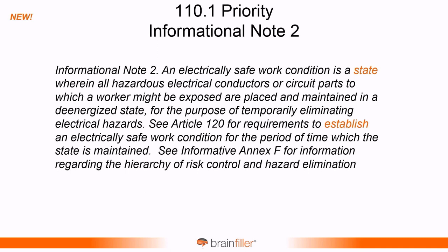There was also an informational note that's new. Informational note number 2 discusses that the electrically safe work condition, again, is a state, and it goes on to describe what that state is. But further down, it references Article 120 for the requirements to establish an electrically safe work condition. So really, we're looking at two different things. We're looking at the state of the electrically safe work condition, and then we're looking at what the requirements are to actually establish the electrically safe work condition.